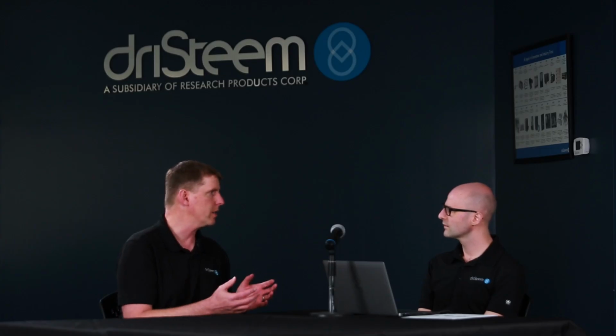Okay, what is my goal again as to where that might be best? But if you don't have the steam available or even water droplets, you'd have to make those. Now you've got additional equipment that you're working through. Going back to that example, if you're trying to do a gas humidifier in the middle of a building, you've got to get the utilities there and then the venting out of the building. Well, if it's in the middle, that may be a challenge. Electricity doesn't have that additional constraint.